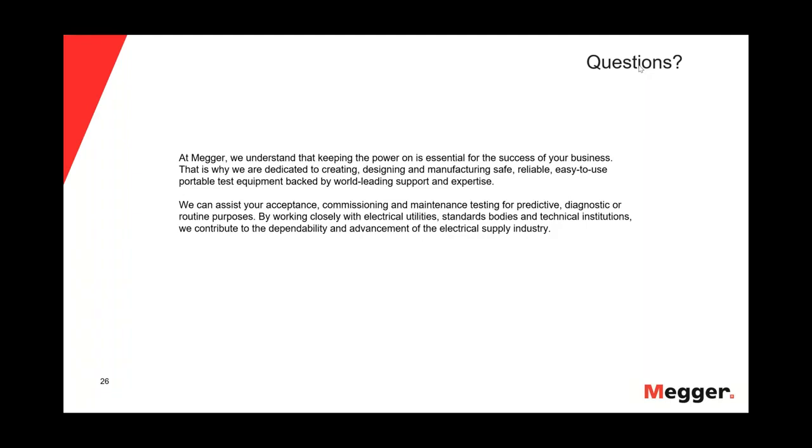Well, I assume he has talked about a three-phase cable with three individual cables. It's very common that all three cables will not show the exact same, let's say, dielectric properties, whether it's tan delta or leakage current or whatever. And that has to do with the fact that when the cables are installed, they're not actually treated identical. So one cable could get some damage that the other two phases don't get. So when you have one phase that sticks out, that is much higher in, let's say in this case, tan delta, that's what we talk about here, then you would have to see what it can mean.